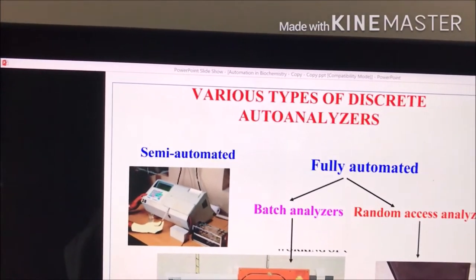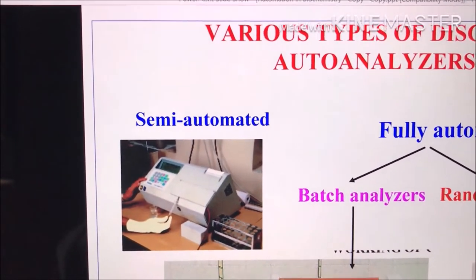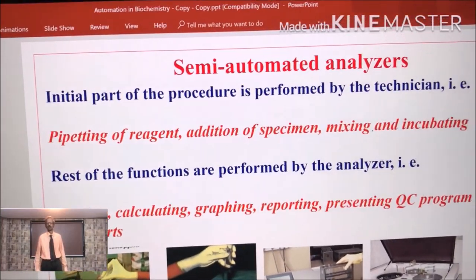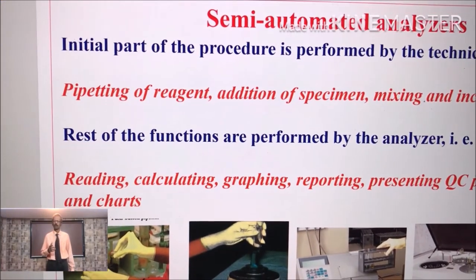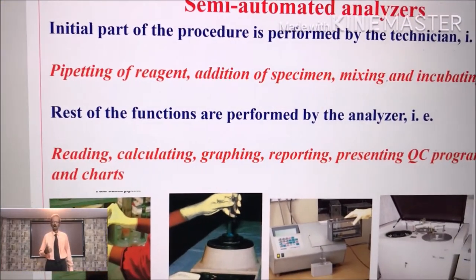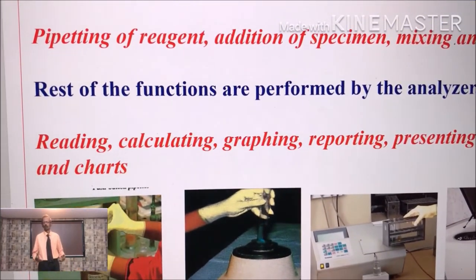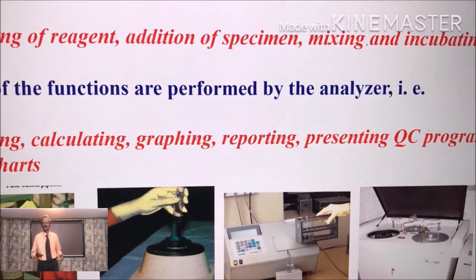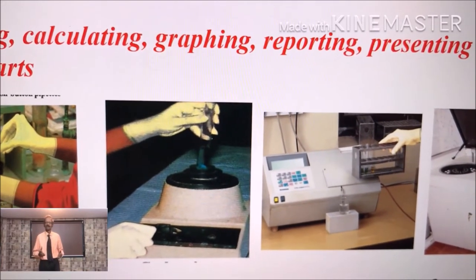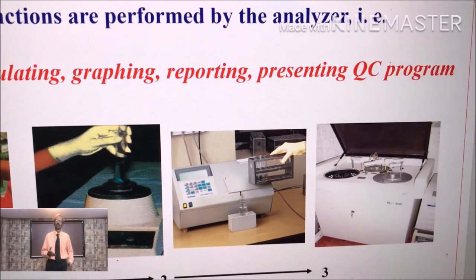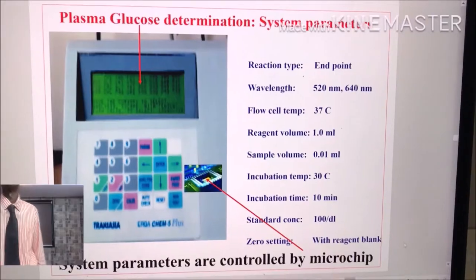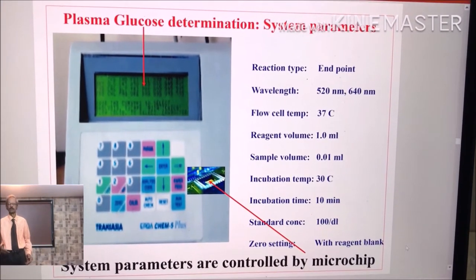And today we are going to discuss about how to use and operate semi-automated analyzers. In the case of semi-automated instruments, initial part of the procedure is performed by the technician. That means pipetting of the reagent, addition of specimen, mixing, incubating and rest of the work. That means reading, calculating, graphing, reporting and presenting quality control charts are performed by the analyzer.